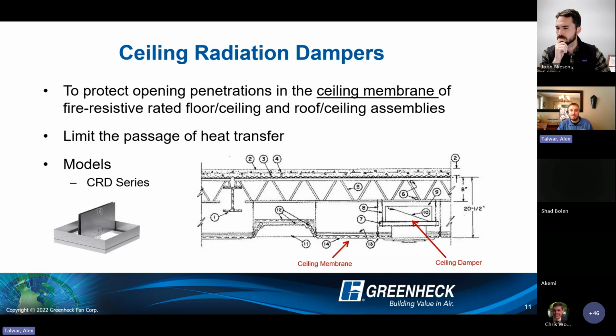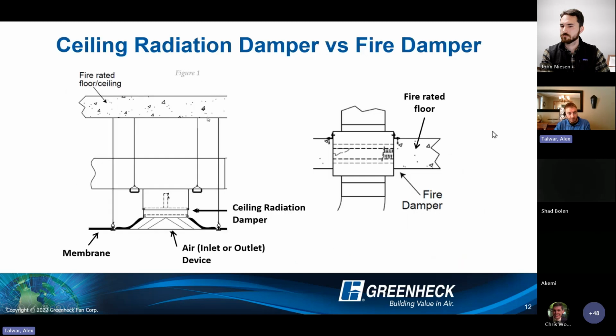Whereas with a fire damper, we're talking about a complete through penetration of a rated assembly. In the case of a ceiling damper, we're only really talking about protecting that initial membrane layer of the floor ceiling or roof ceiling assembly. And again, we're talking about limiting passage of heat transfer, not complete flame through or protection in that regard. So just something to keep in mind there.